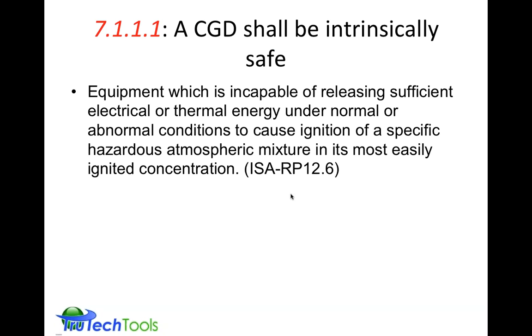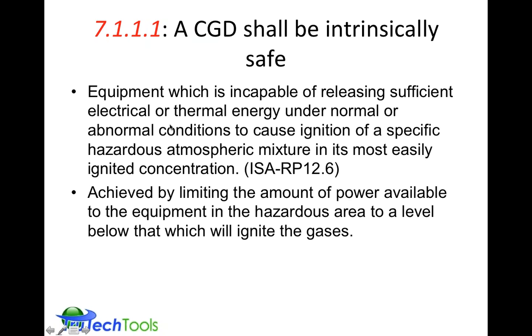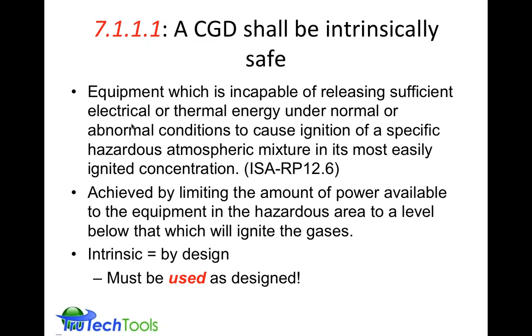The statement that it must be intrinsically safe means, the intrinsically safe definition is, it's incapable of releasing enough energy under normal conditions to cause ignition of a specific atmosphere. So this comes right from the International Standards Association, or Instrument Standard, ISA, I believe it's Instrument Standards of America. I'll have to double check that, it's been so long. That's the standard definition for an intrinsically safe product. It limits the amount of power that goes through the equipment and can reach the gas in the atmosphere, which would cause the potential for an explosion.